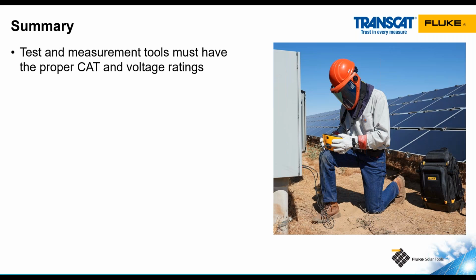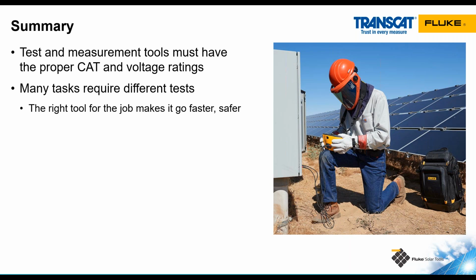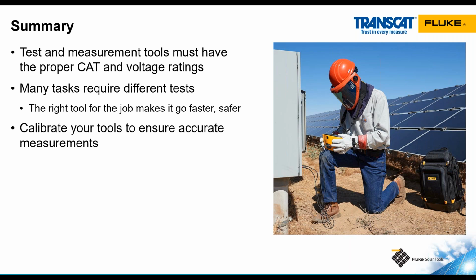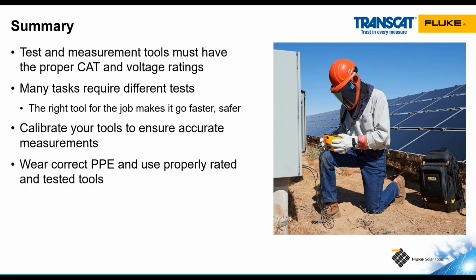So to summarize, we need to make sure that our test and measurement tools have the proper category rating for the environment in which we are going to be working, either category 3 on the DC side of the system or category 4 on the AC side of the system, especially if we're close to the utility. And it needs to have a voltage rating above the voltage of the system that we will be working on. Fluke has a wide range of tools designed for many different tasks. If you have the right tool for the job, it's going to go faster and it's going to be safer for the technician and give you better results. But we have to calibrate our tools on a regular basis to make sure they're getting proper measurement results.